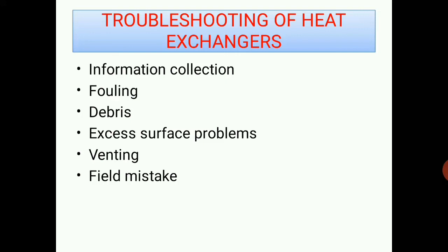Excess surface problems: in the design stage, the clean condition may not have been evaluated. Many exchangers are designed for fouled condition only. The next one is the venting. Proper venting is a startup necessity. Improper venting usually occurs on startup and is recognized by poor heat transfer and a high pressure drop. The field mistakes: in one instance a heat exchanger was piped up backward, and the fluid that should have been on the shell side was piped to the channel side and vice versa. So this is all about the heat exchangers.